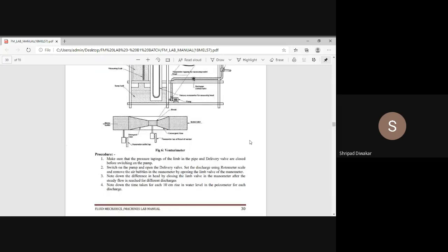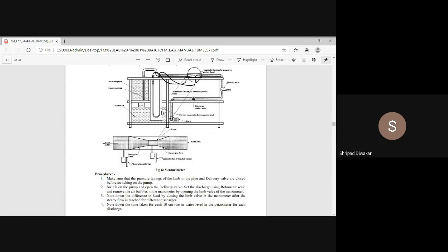Okay. So as I said, manometer is used to measure the pressure difference. Okay, you are seeing this is the mercury manometer. Mercury is used as a manometric fluid because of its unique properties, like it has a low coefficient of thermal expansion, so it is a heavy liquid. It does not stick to the walls of the tube. Okay, and we can easily read the readings by using mercury as manometric fluid, and it is mainly used to measure the pressure difference between 2 points.